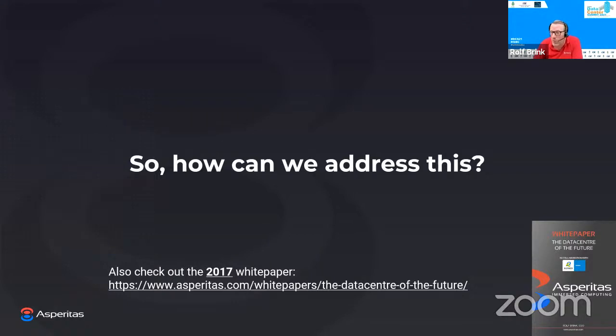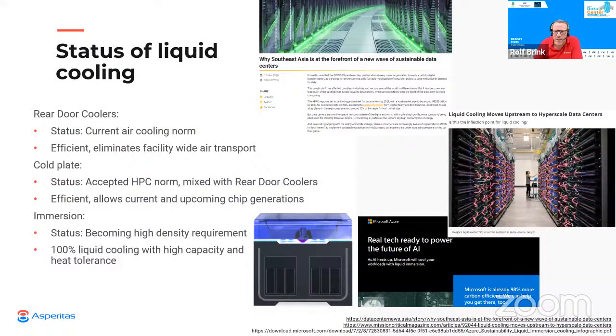The most well-known form of liquid cooling now relates to rear door coolers. These are water-cooled heat exchangers which act as air handlers at the rear door of the rack, and these are efficient and eliminate the need for facility-wide air transport. These are already the new norm for air cooling and are integrated in the new rack standards, especially within OCP.